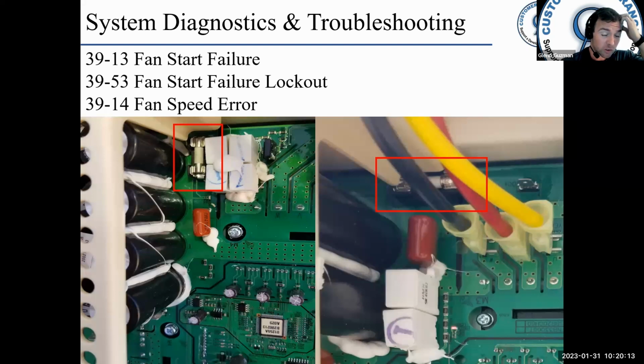Okay, you actually will see 8815 accompany a lot of different faults because the VFD is being reset by the PCM. The PCM continues to reset the VFD up to 6 times, and then it will eventually declare 3953 and lock the unit out for 1 hour. A successful fan start will reset the fan fail start counter, and it will start all over again.